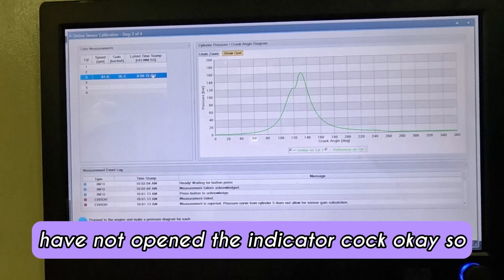The alarm has been accepted, and now they're going to just start for the other unit. It just says ready and waiting for button press. Measurement started, waiting for sensor to reset, and now it's waiting for the measurement to come in. So let's see what cylinder they have installed. They've done it for cylinder number 2, and we've got the curve for cylinder number 2. So it's pretty simple and pretty easy task, which needs to be done as part of the MAN B&W circular. Read through the circular and complete this as a 6-monthly procedure.